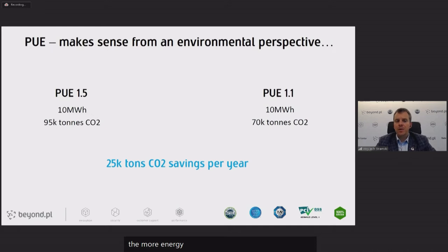And so measuring PUE actually makes a lot of sense from an environmental perspective. If you take a customer that has a requirement of 10 megawatt hours, that customer can save 25,000 tons of CO2 per year just by drawing from a PUE ratio of 1.1 versus a PUE ratio of 1.5.